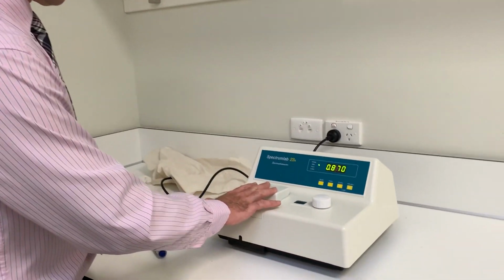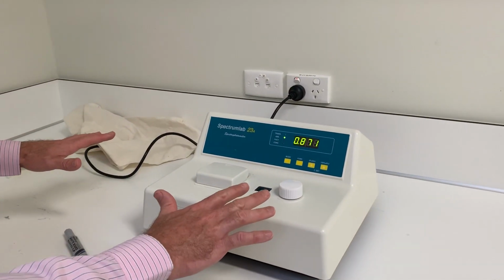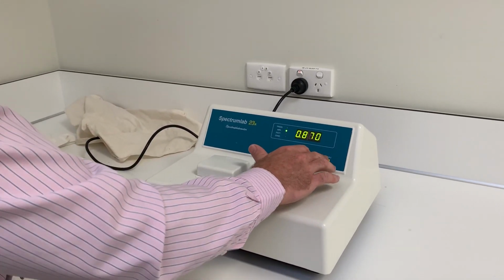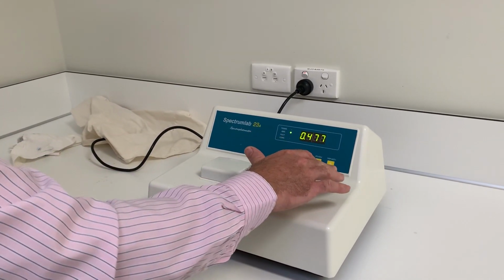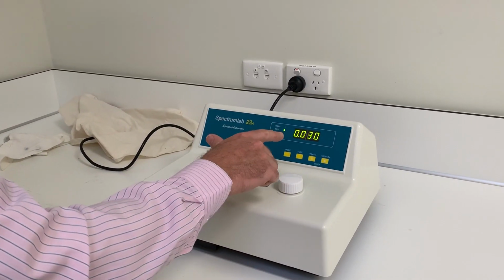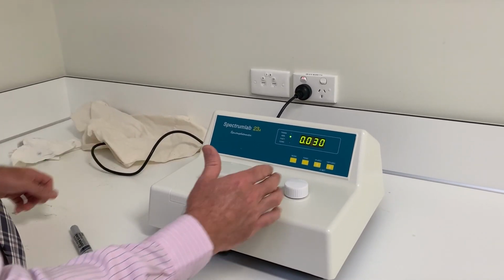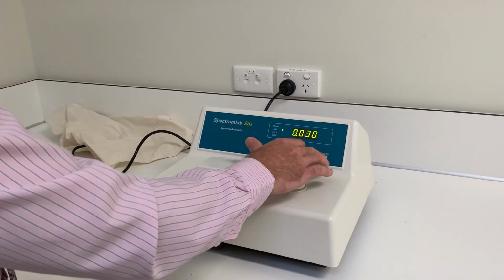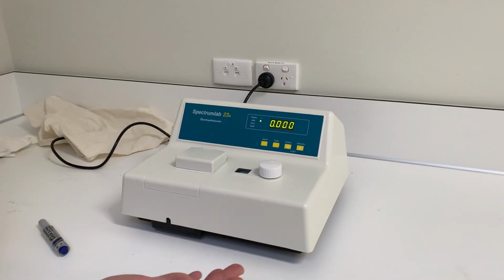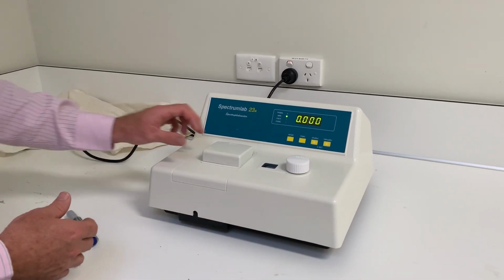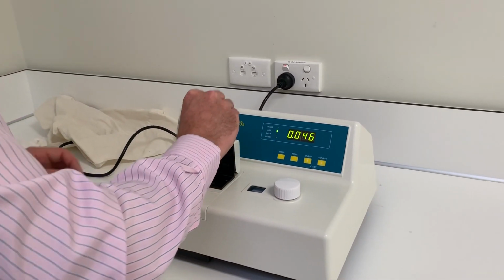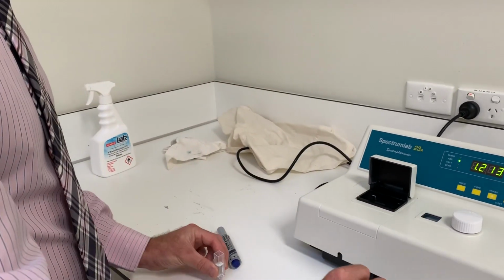Now the very first thing we do need to do, just like zeroing a mass balance, we need to zero this. And if you press 100% adjust, it'll go down to 0. It should go down to 0, but you'll notice that it hasn't quite gone down to 0, so I'm going to press 100% adjust again, and it's on 0. Now what we can do is we can take that out.